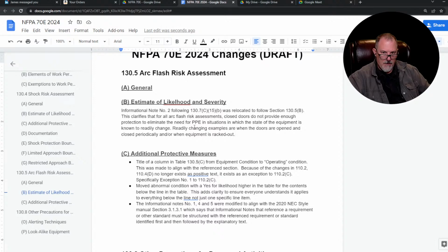Doors open. What the heck's a door? Yeah, and so the problem I have with this is, it says a common misconception is that even in non-arc resistant equipment, closed doors remove the need for PPE. This informational note relocated clarifies that closed doors do not provide enough protection to eliminate need for PPE.